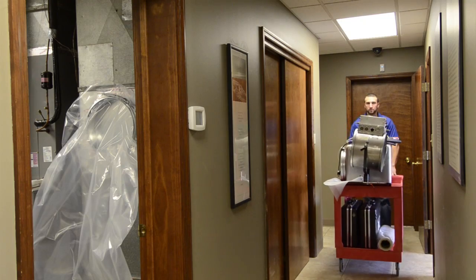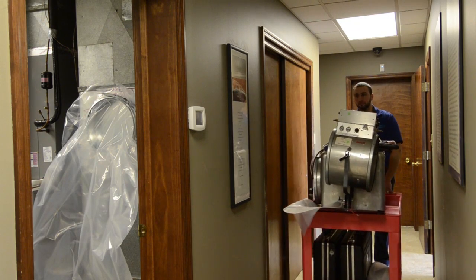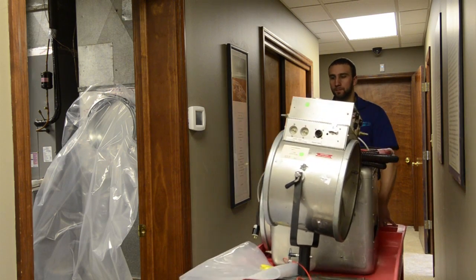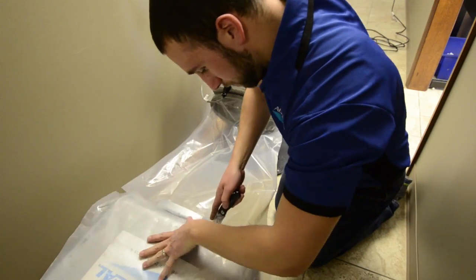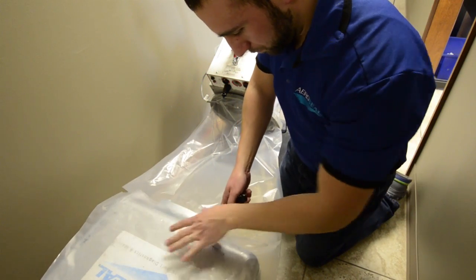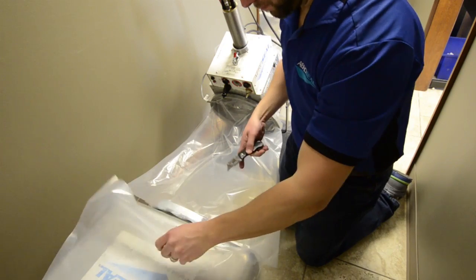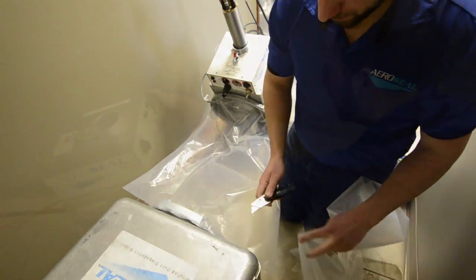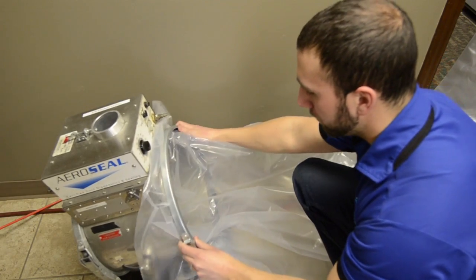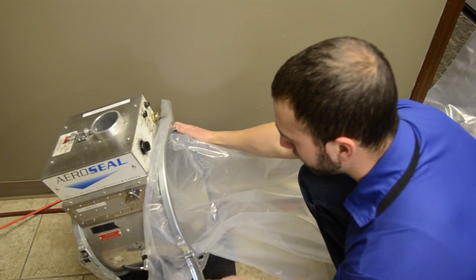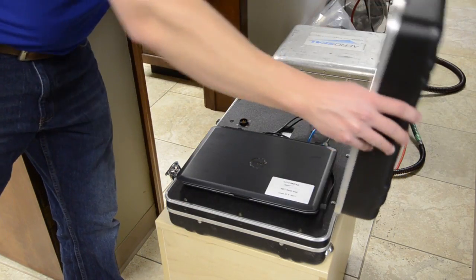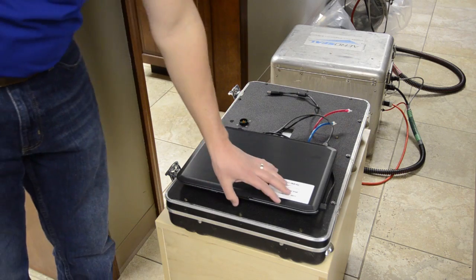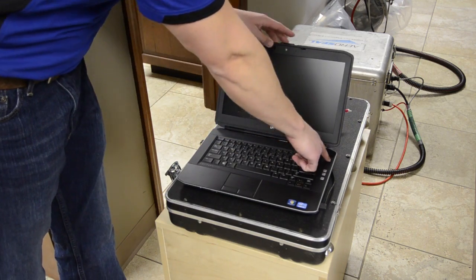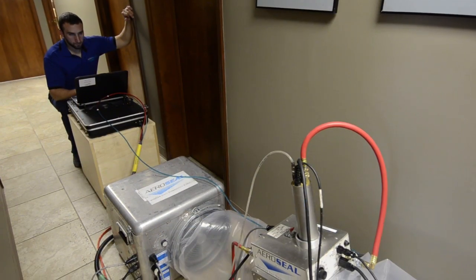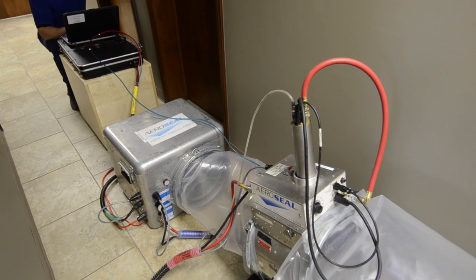The Aeroseal sealing process starts with our equipment being set up directly at the first injection site. Lay-flat tubing should be cut to 2 or 3 foot length to comfortably reach from the fan box to the heater cylinder. The tubing is then connected on both sides using 14-inch clamps. The computer, which controls the entire Aeroseal operation, is set up and connected to the Smart Seal equipment. Be careful to keep it a safe distance from the sealant and heater fan.